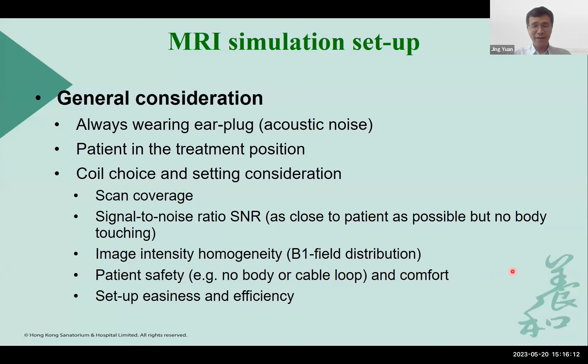So it is easy to understand for the RT professionals. And regarding the coil choice and setting, we have to choose a coil whose scan coverage is not too big and not too small. We also need to choose and place the coil to maximize the signal to noise ratio and minimize the scan time. We also need to consider other factors such as image intensity, homogeneity, patient safety and comfort, and setup easiness and efficiency. I will explain these items in detail in the following slides.